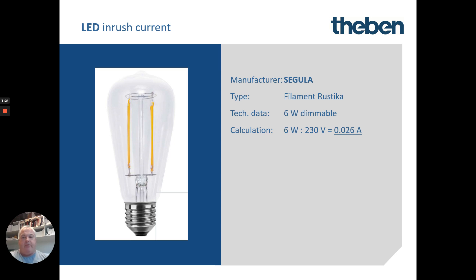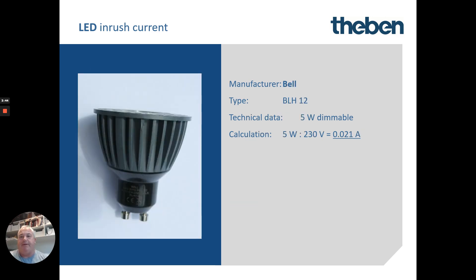We can go through a number of manufacturers. Here we have one that is 6 watts to run drawing as little as 0.026 amps, and on startup for that very quick moment it's actually pulling 5.8 amps — which is 220 times higher than the run current. And so on and so forth — you'll see similar patterns with a lot of LEDs.